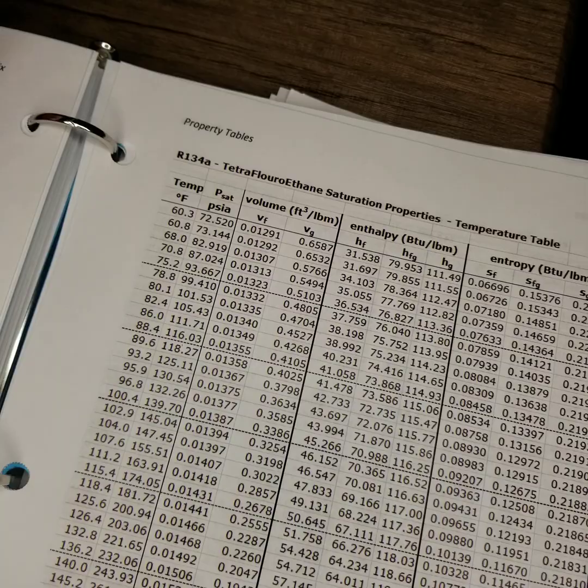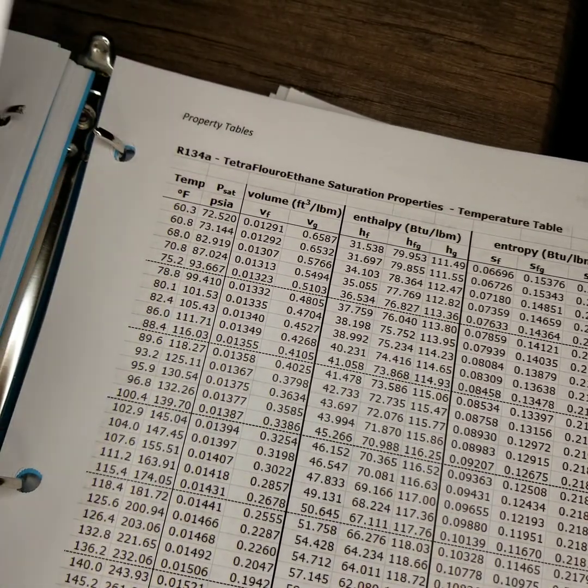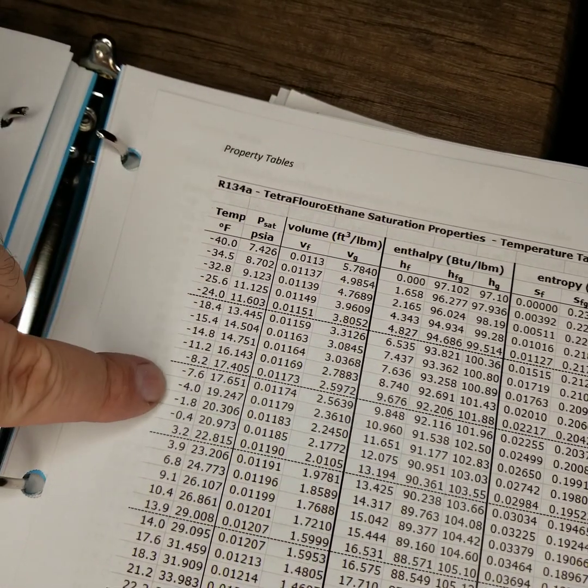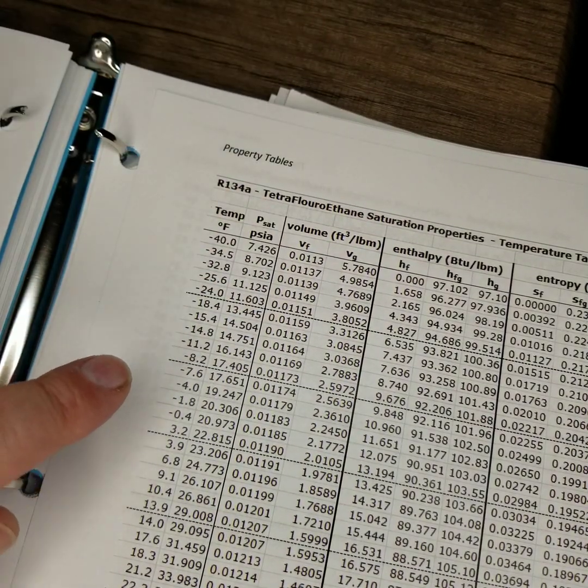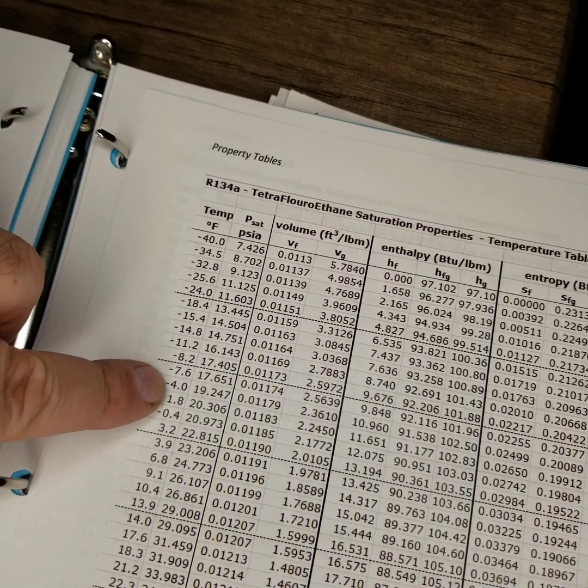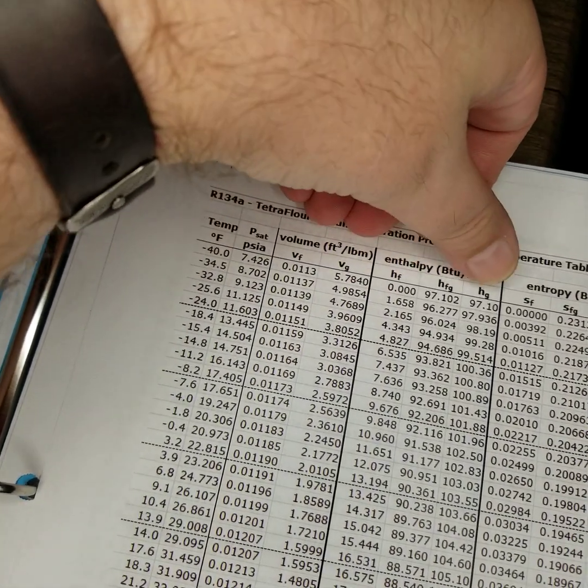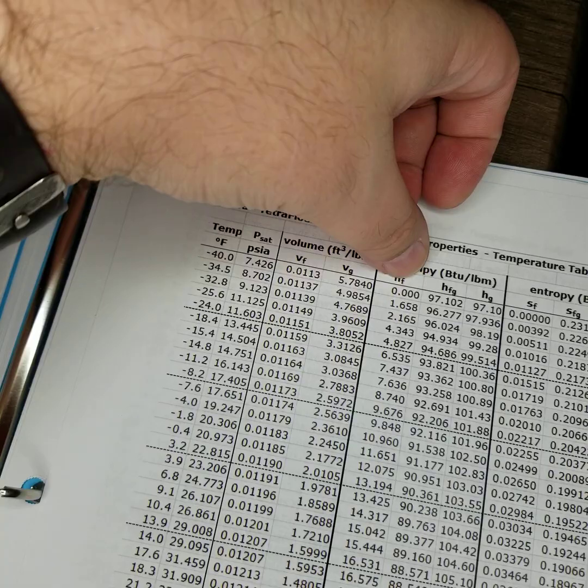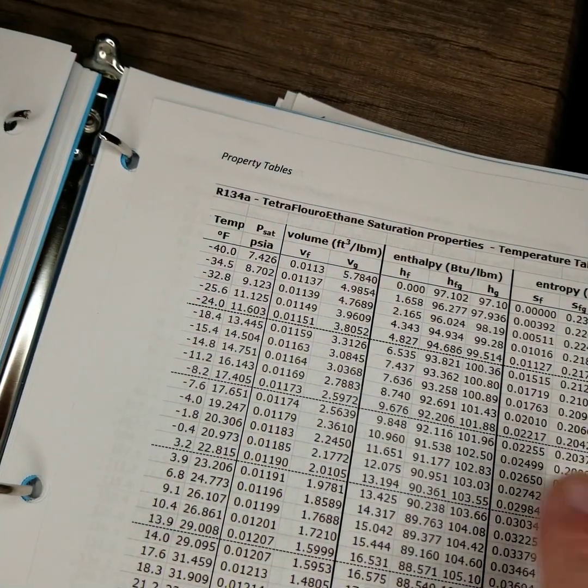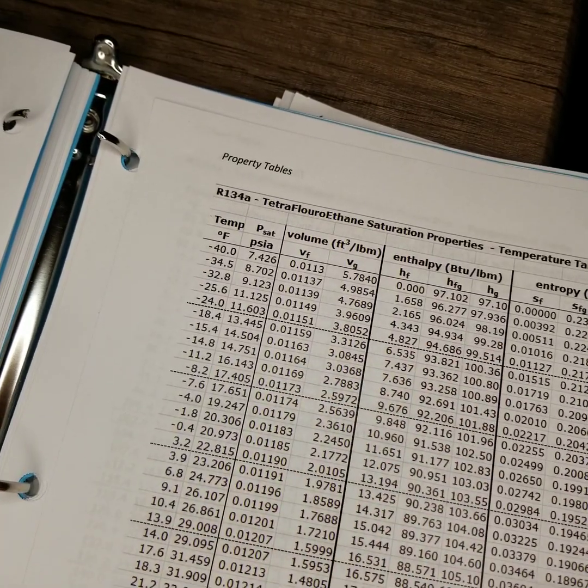So let's look up the enthalpy of a saturated vapor at minus 4 degrees Fahrenheit. I'll just pull this page over here. So minus 4 degrees Fahrenheit, we have to convert to Rankine for this, and this is saturation properties, and it's asking for a saturated vapor. So as you recall from previous classes, H sub F is a saturated fluid. H sub G is a saturated vapor or gas. H sub FG is the enthalpy required to convert from a saturated fluid to a saturated gas. So this middle column enthalpy is basically that flat line between your saturation points on a temperature entropy diagram.